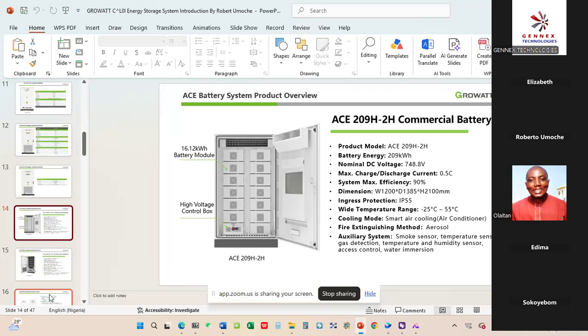And then this particular battery, the nominal voltage is 748.8 volts. That is the nominal voltage when the battery is not connected to either PV or the grid. So when you connect all of them in series, you should have 748.8 volts. So if you receive this battery and you test it and your voltage is below this, maybe one of the modules is faulty, or the connection is not right, so you need to review it.